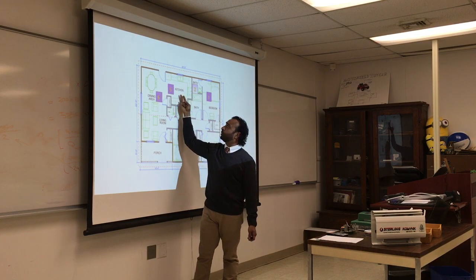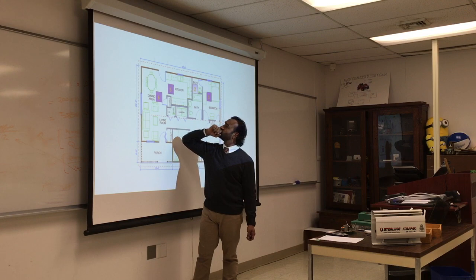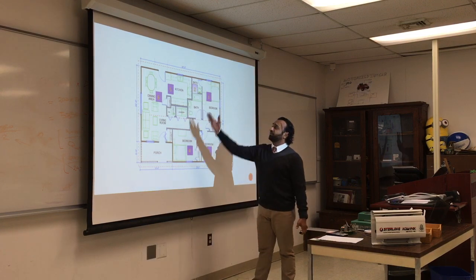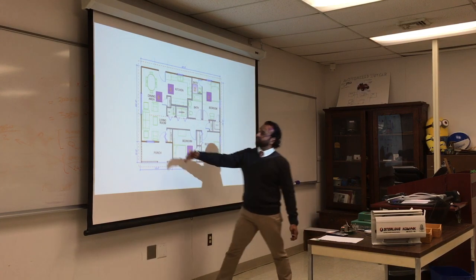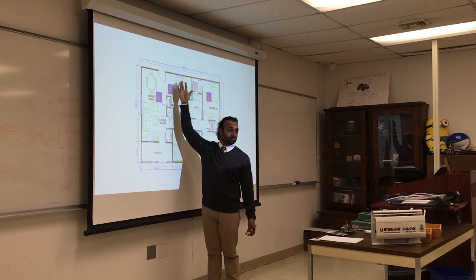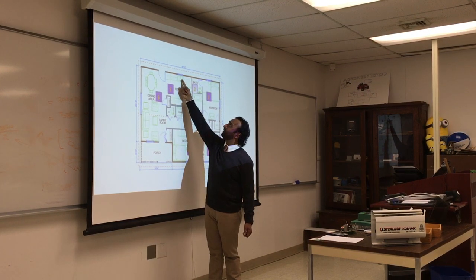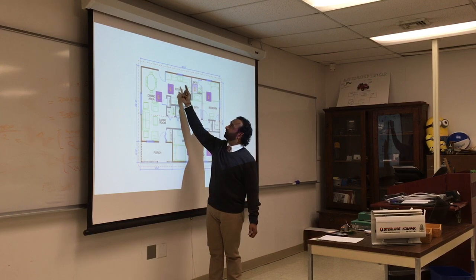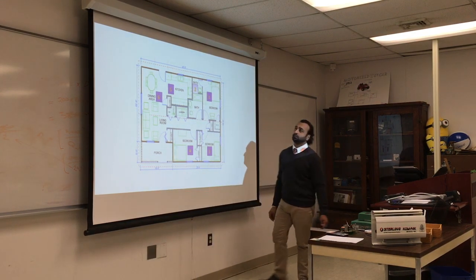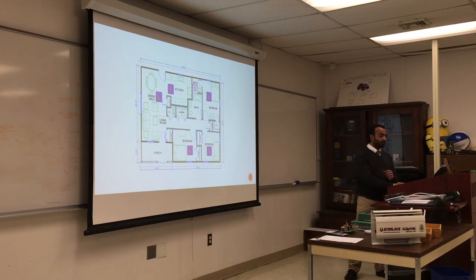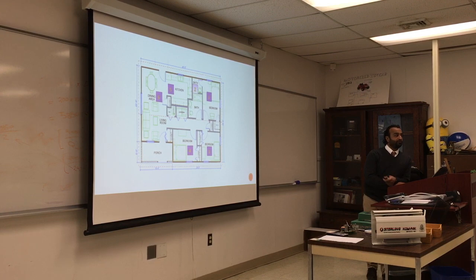So for here, either you're going to have a kickboard radiator. But why can't we do our calculations for heat loss as one big room? You could, but I don't think it will get sufficient heat this way. Really? Because this is completely open to each other. You're going to have to put some kind of fans to push the air here. Otherwise, it's going to be significantly colder than the other side, especially if you have a window here. So you might need some kind of heat source in the kitchen. But our calculations would still come out the same if you treated them separately, right? It's going to be the same. Close enough. But then afterwards, go through and add kickboard radiators. And in the kitchen, you're always going to have a lot of fans and vents, so you need to get some kind of heat source. Probably not much, but you need something.